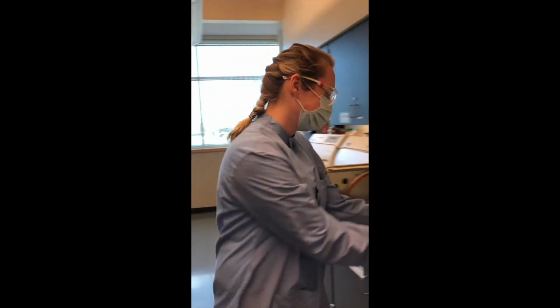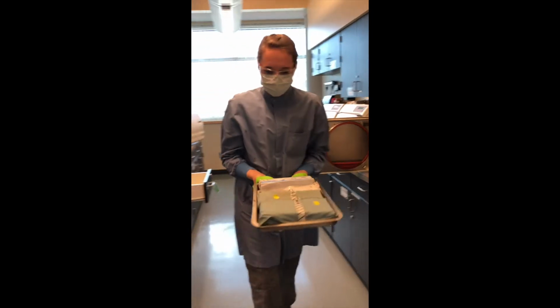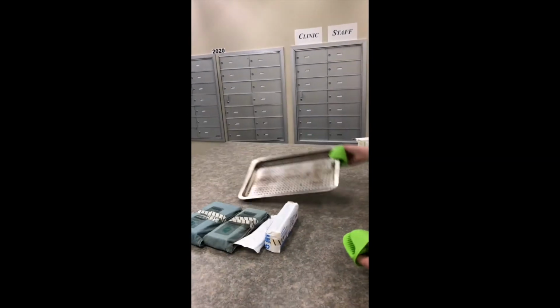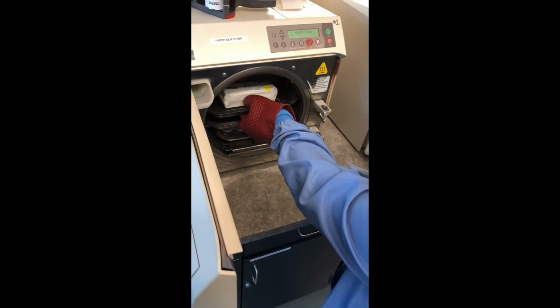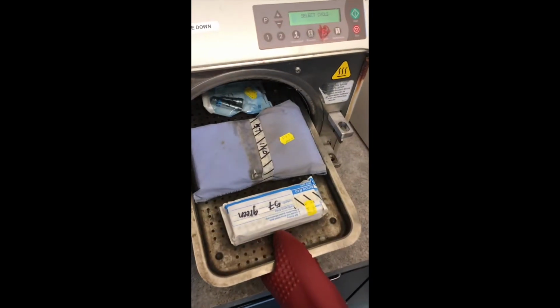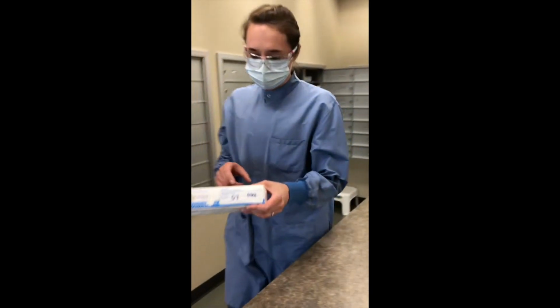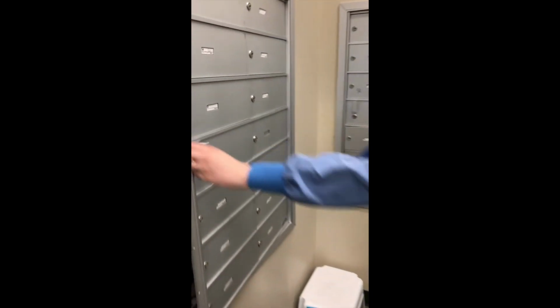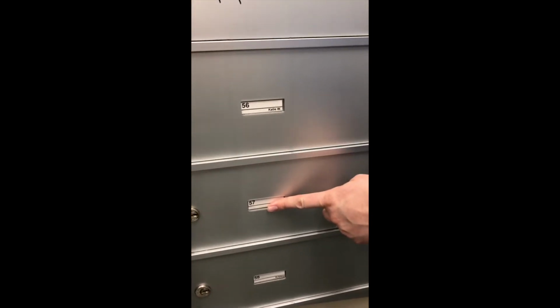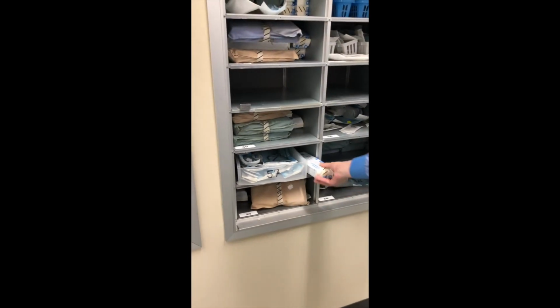When autoclave cycle is complete, use clean hands and pot holders to remove hot trays from the autoclave. Dump hot trays onto clean counter in the sterilization storage area. While unloading the autoclave, it is important to make sure that indicator strips have changed color, showing that the process was successful. After instruments are completely dry, they should be placed in students' corresponding steri boxes. Note the number on the front of the package and find the corresponding locker.